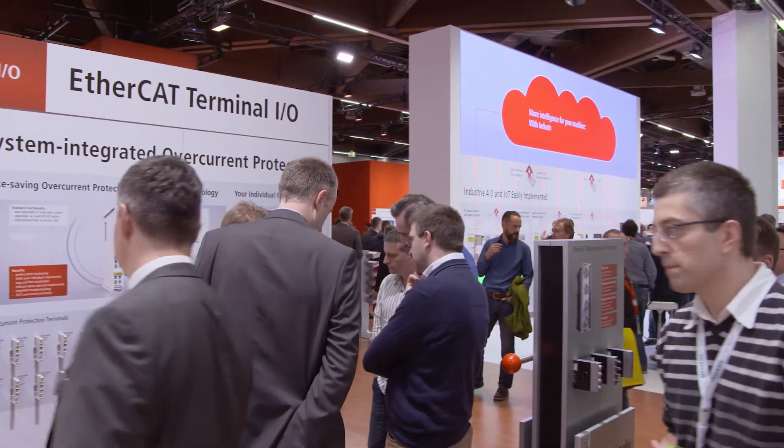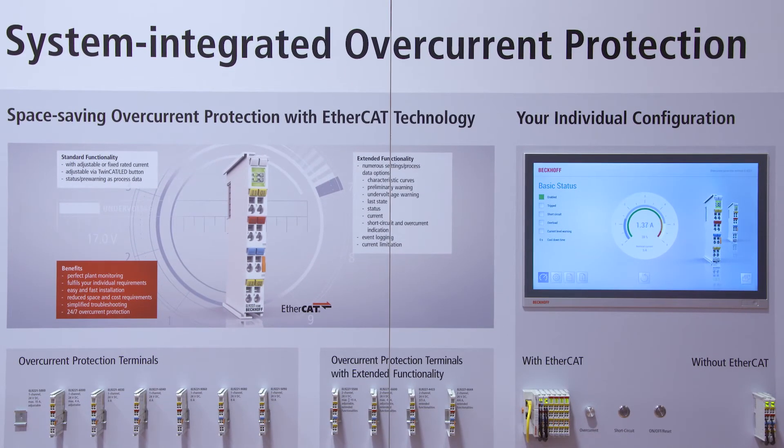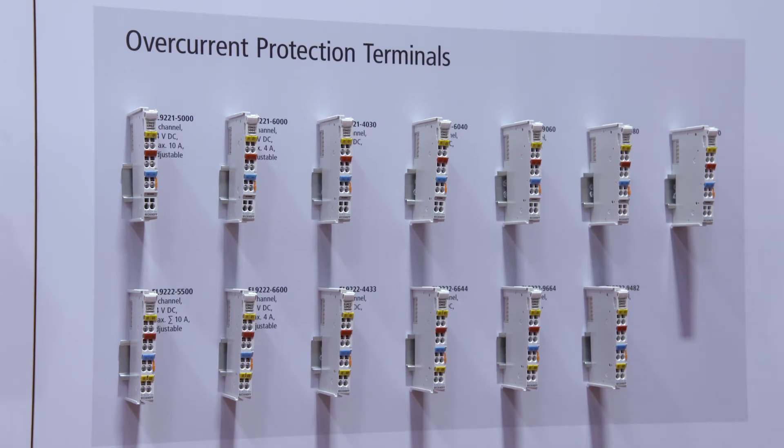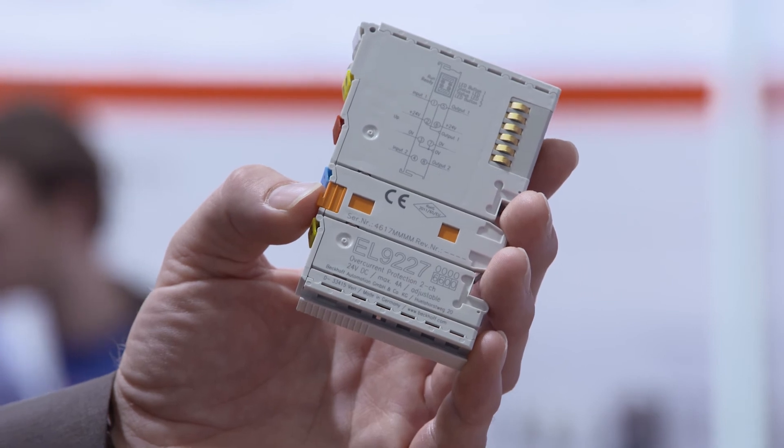With a new range of terminals, electronic overcurrent protection is now an integrated function of the EtherCAT I/O system. The new overcurrent protection terminals reduce external fuses and fieldbus gateway products, saving installation time, costs, and space in the control cabinet. The portfolio includes one and two channels up to 10A with adjustable and fixed values. The terminals with standard functionalities provide status and pre-warning info via LED and process data. The terminals with extended functionalities offer an adjustable characteristic curve, and internal current measurement technology enables plant monitoring for a transparent inside view of the system.